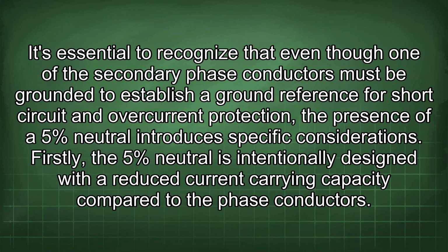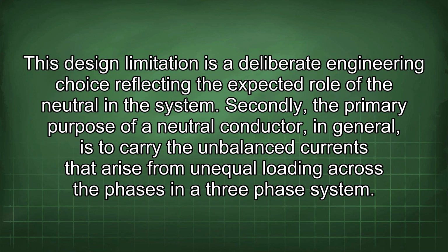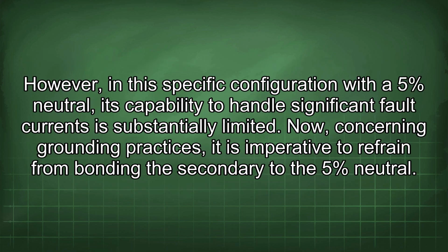Firstly, the 5% neutral is intentionally designed with a reduced current carrying capacity compared to the phase conductors. This design limitation is a deliberate engineering choice reflecting the expected role of the neutral in the system. Secondly, the primary purpose of a neutral conductor, in general, is to carry the unbalanced currents that arise from unequal loading across the phases in a three-phase system. However, in this specific configuration with a 5% neutral, its capability to handle significant fault currents is substantially limited.